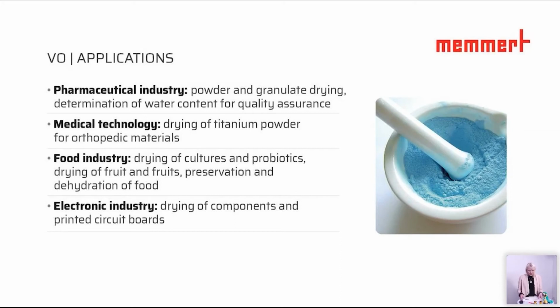Next one. Let's go on to some applications. As I already mentioned, in the pharmaceutical industry, a vacuum oven is mostly used. That is for drying purposes of powder and granulate, but also for the determination of water content for quality assurance. Here, I would like to give you an example of the gel capsules. The gel capsules must have a certain softness. Otherwise, you cannot use them. And that means there are certain rules and regulations available. That is, for example, standard 731 from US Pharmacopoeia or USP 921. And here the moisture content is mentioned. And that means to have a convenient dryness and moisture content below 13 to 16%, a vacuum oven is needed. That is not possible to be done with any other product.